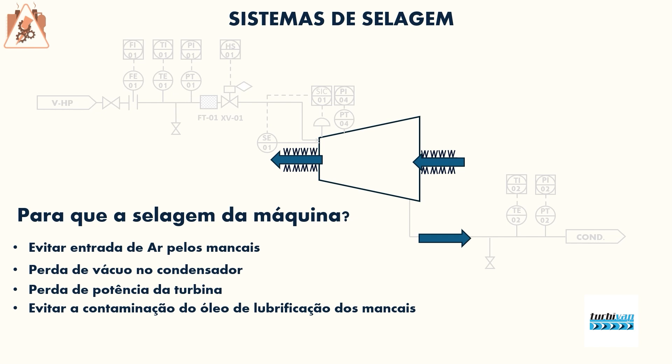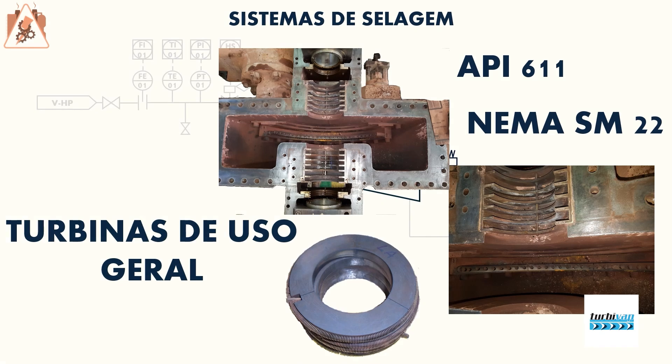Steam coming out mainly from the high pressure bearing on the left turbine bearing can contaminate the turbine lubrication system. Water and oil do not mix, so the result is contaminated oil with water, which leads among other things to corrosion in the bearing system and changes in viscosity — in short, a big problem.